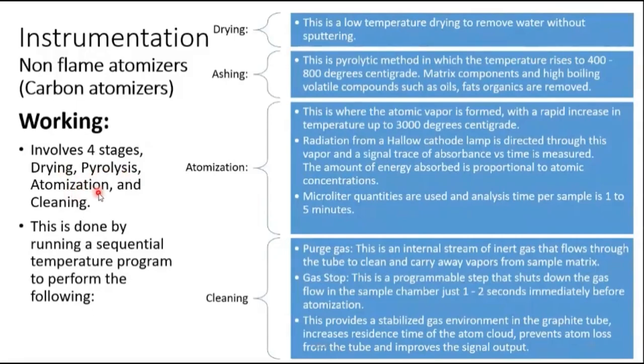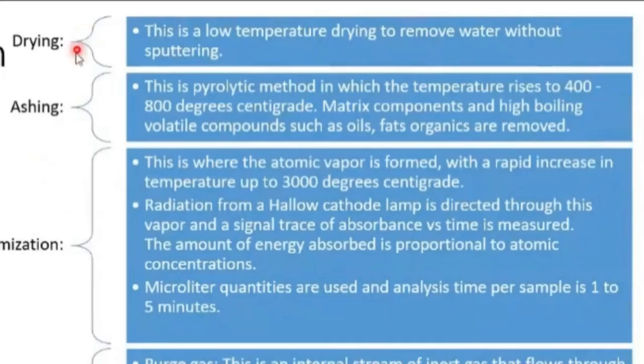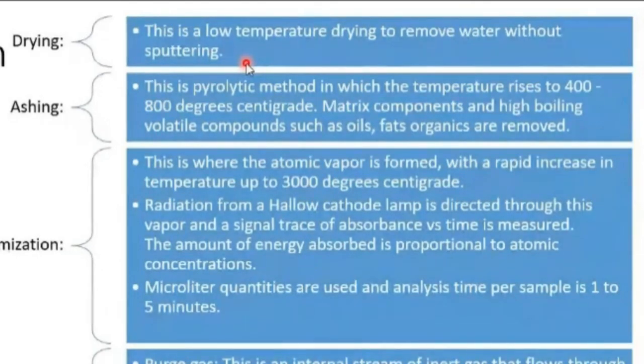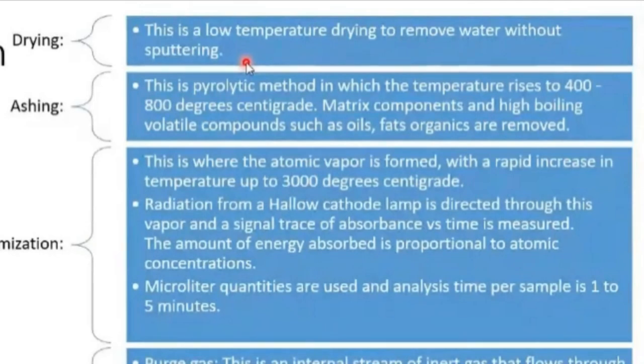This is done by running a sequential temperature program. Step one — drying: this is low-temperature drying to remove water or solvent without sputtering. Sputtering is what happens when you heat a pan and add a drop of water — the drop starts dancing and small droplets sputter around. That sizzling action is called sputtering.